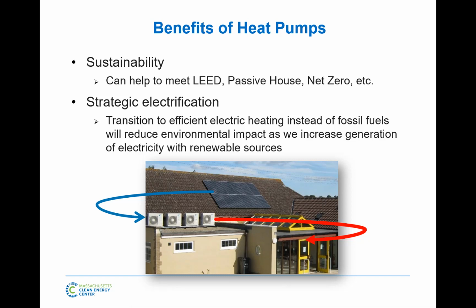But it's also because what's the alternative? If you want to heat with electricity, you can put baseboards everywhere. That's 100% efficient, COP of 1. The problem is electricity is very expensive, so it'll cost you a whole bunch of money. You put an air source heat pump in with the same amount of electricity, you can deliver 2, 3, 4, 5, or 6 times more heat. We'll talk about that in a minute. So that's why air source heat pumps are so popular. It's the way to electrify your building on the HVAC side.